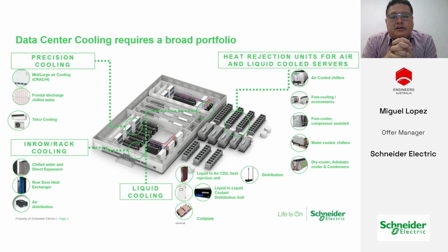And on the far right-hand side is your outdoor heat rejection. In Australia, in the Pacific zone, this typically involves air-cooled chillers. If the design calls for it, we also have the option of incorporating free cooling air-cooled chillers. The need for free cooling, or not to free cool, will be explained in the next few slides. There are also free cooler compressor-assisted systems, water-cooled chillers, and lastly dry coolers with adiabatic systems to cater for those very high ambient temperatures we have, especially in the center parts of Australia. Temperatures get very, very hot, so adiabatic systems are required.